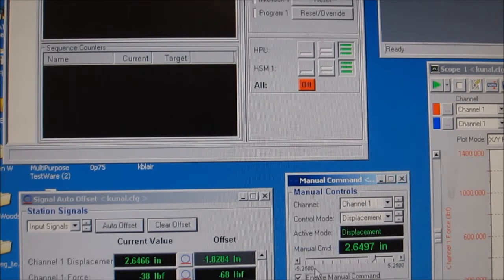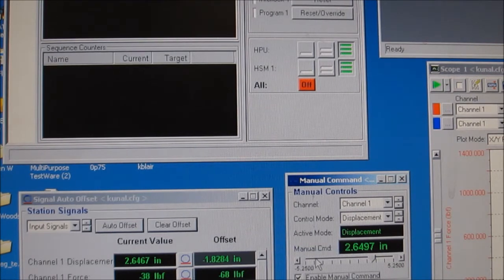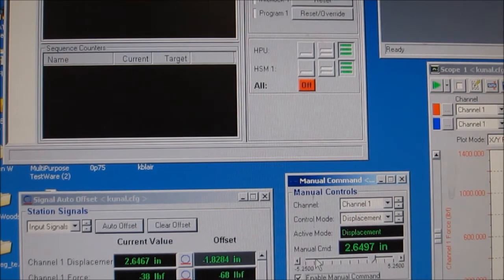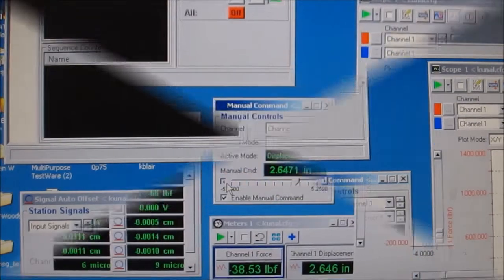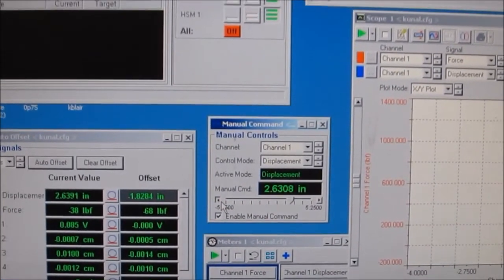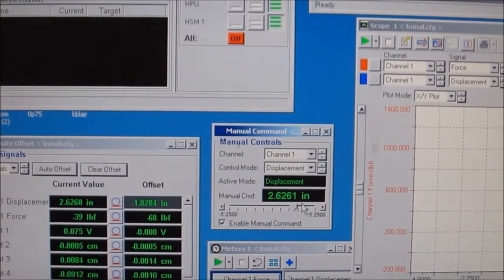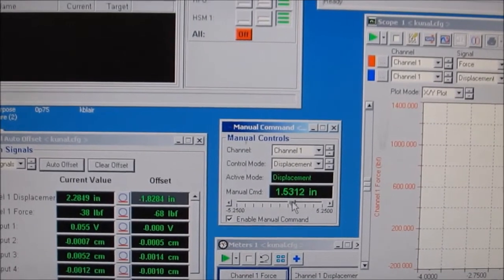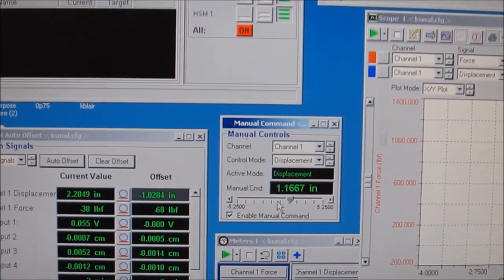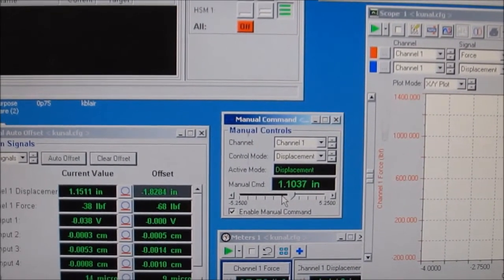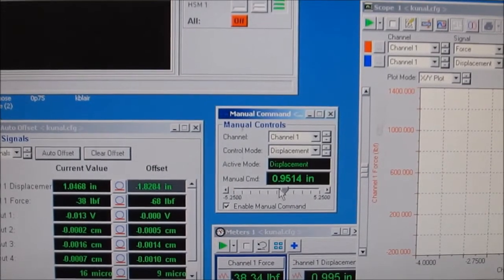Now you have the ability to enable manual command. Either by clicking the arrow buttons, holding down on the slider, or dragging the slider left and right in the manual command window, you can actuate the hydraulic piston on the MTS machine.